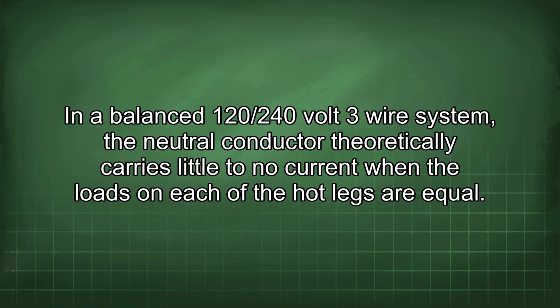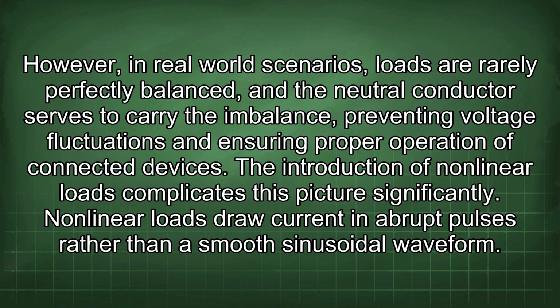In a balanced 120/240 volt 3-wire system, the neutral conductor theoretically carries little to no current when the loads on each of the hot legs are equal. However, in real-world scenarios, loads are rarely perfectly balanced, and the neutral conductor serves to carry the imbalance, preventing voltage fluctuations and ensuring proper operation of connected devices. The introduction of nonlinear loads complicates this picture significantly.